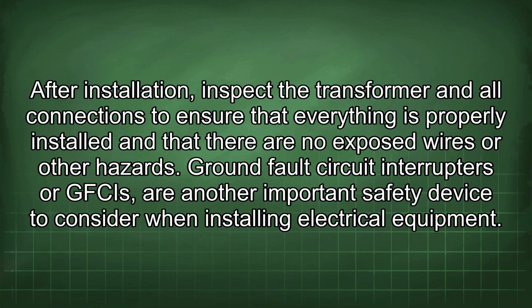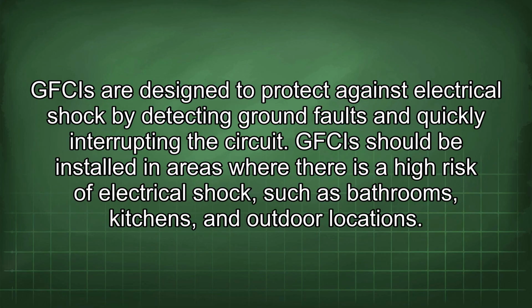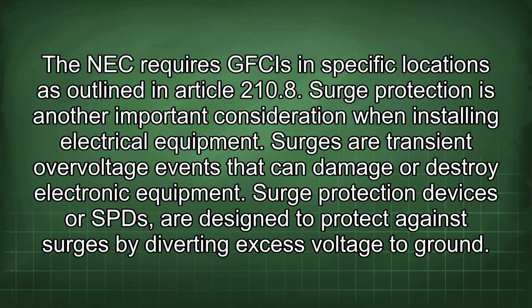Ground fault circuit interrupters, or GFCIs, are another important safety device to consider when installing electrical equipment. GFCIs are designed to protect against electrical shock by detecting ground faults and quickly interrupting the circuit. GFCIs should be installed in areas where there is a high risk of electrical shock, such as bathrooms, kitchens, and outdoor locations. The NEC requires GFCIs in specific locations as outlined in Article 210.8.